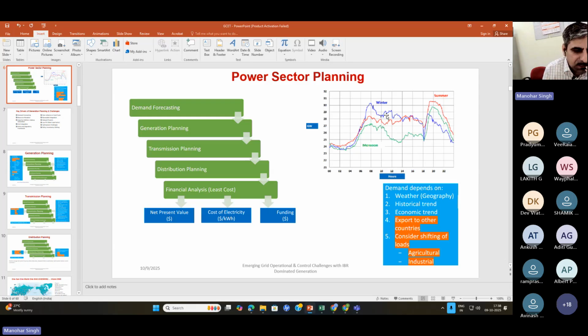Now the operator comes into action. Since 50% of the power still comes from thermal, hydro, or nuclear power plants, they have alternators, synchronous machines. All of them are essentially the same, just with different inputs, but the same underlying resource. Since the machine, the alternator, is the same, it has the inherent characteristic of frequency control through the governor. The governor comes into action and manages the situation depending on the governor droop control.